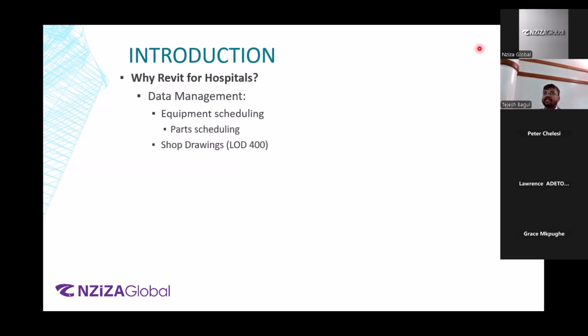Now 300 is basically for the construction documentation. That is where you take into consideration, let's say, how much space is required for the hangers to hang, let's say, a cable tray or maybe conduits, right? If sleeves need to be made in beams, all right, that is coordinated with the structural engineer, and then there is proper allocation of that sleeve in that beam taken into consideration. As you go on to level 400, that is where what actually will be constructed on the field is taken into consideration. Your hangers, your clips, your accessories, everything will get into the Revit model at that time. That is when you'll have LOD 400.